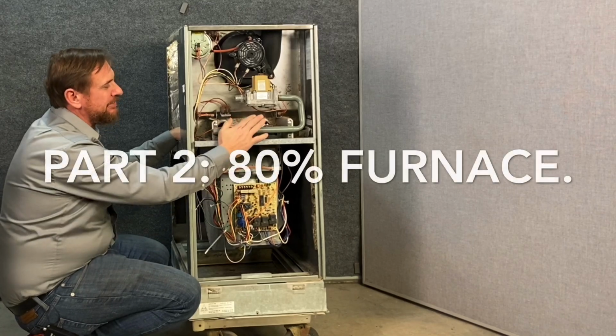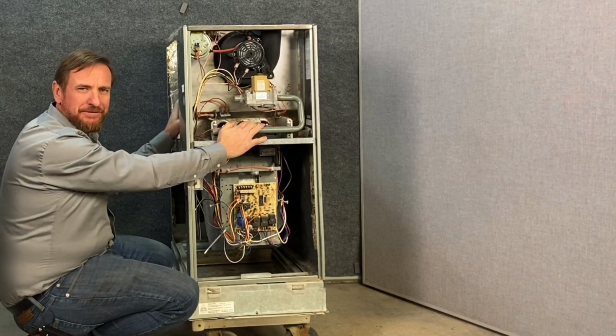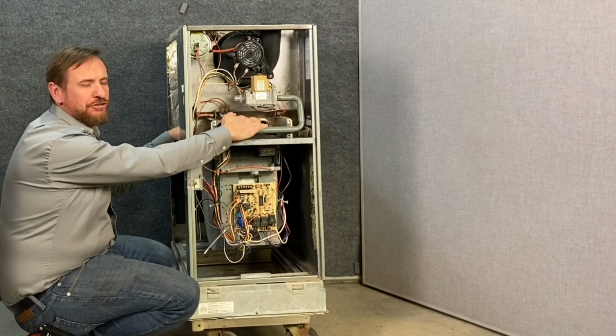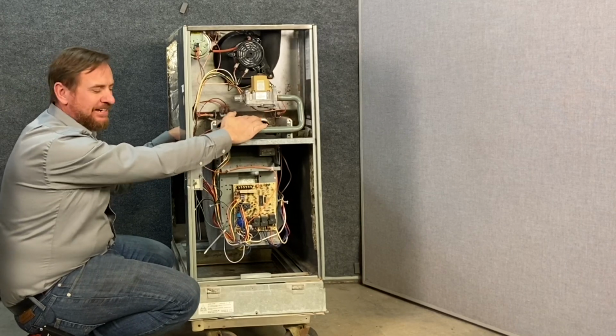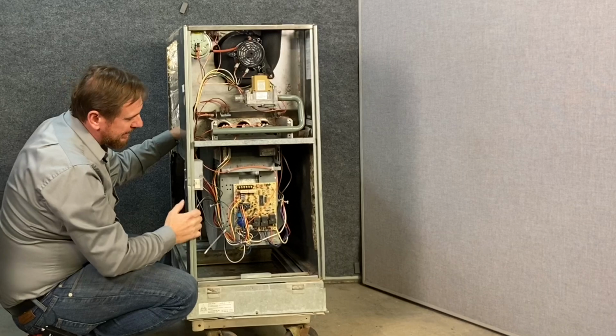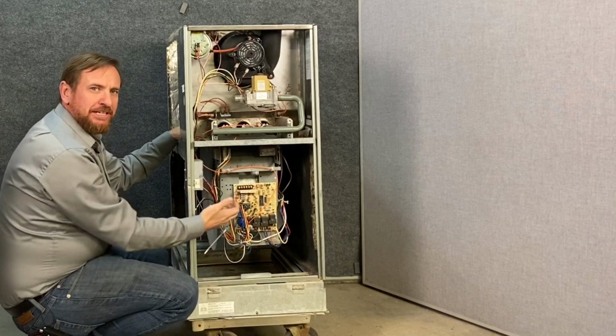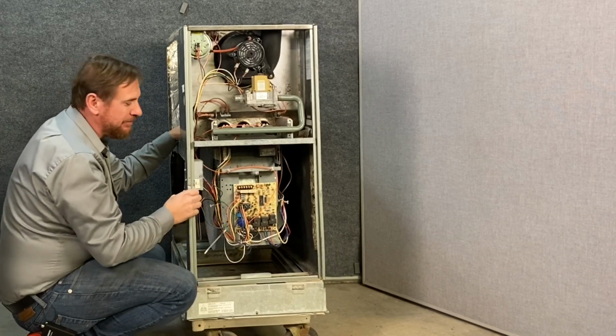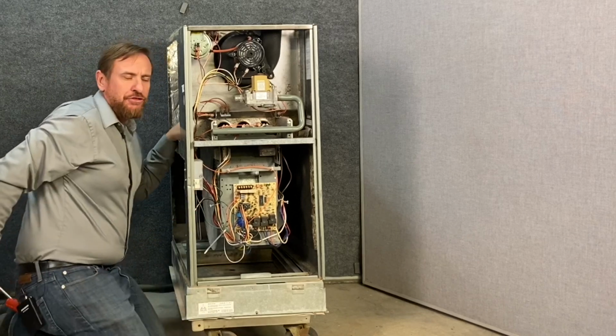This particular model is a RUUD system, RUUD, depends on how you want to pronounce it. It has a direct spark ignition, or what we call a DSI. So we're going to start down at the very bottom side here. If we were going to do maintenance on this, we need to pull this system out so that we could clean the motor. So what we're going to do is we're going to go through those steps.